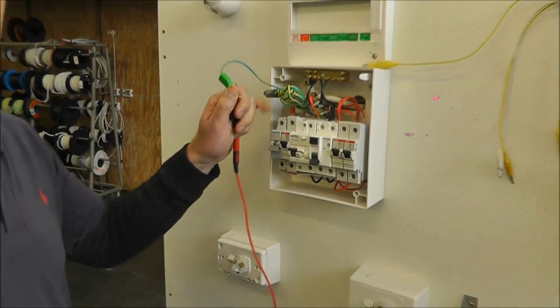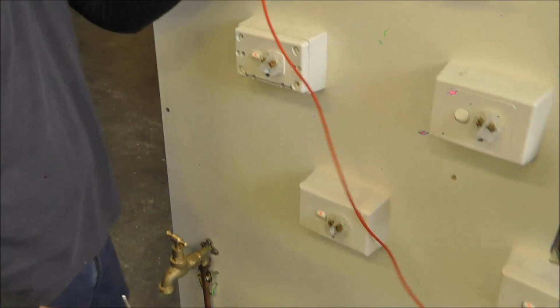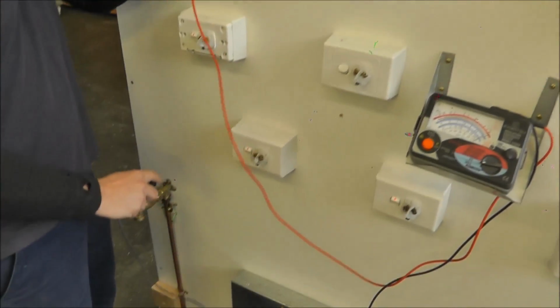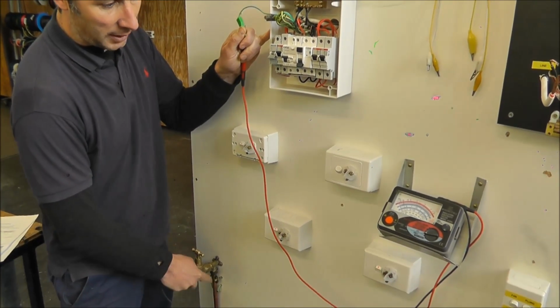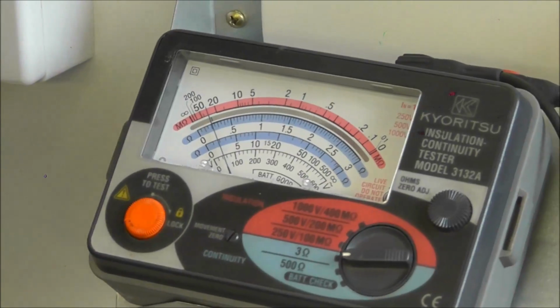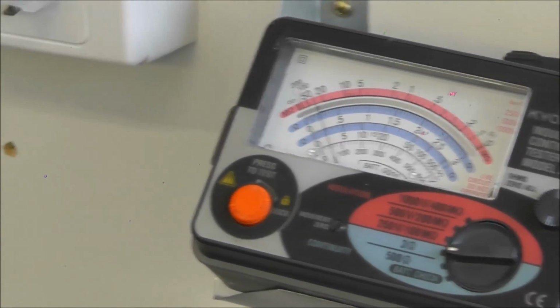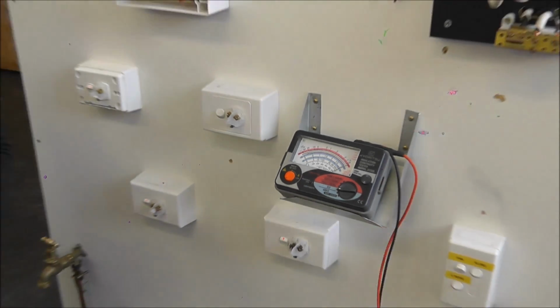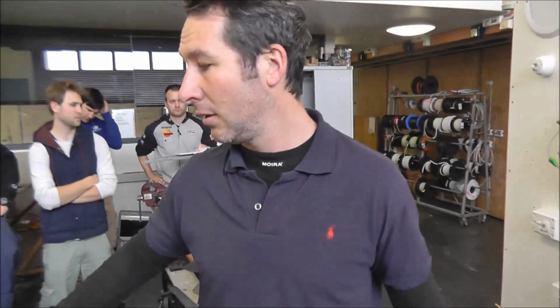Here, what's the next bit? Has anyone got testing charts here, apart from Smitty? What do I got to do now, Smitty? Water pipe. I'm always going back to 3 ohm. I just like to start at 3 ohms. Bonded parts? Yeah. See my meter there? What am I reading on my meter? I'm reading on the 3 ohm scale, like 0.2 of an ohm. 0.2 of an ohm, I'll pop that down. That would be a pass or fail for anyone that knows. Pass. What's the acceptable reading? 0.5.